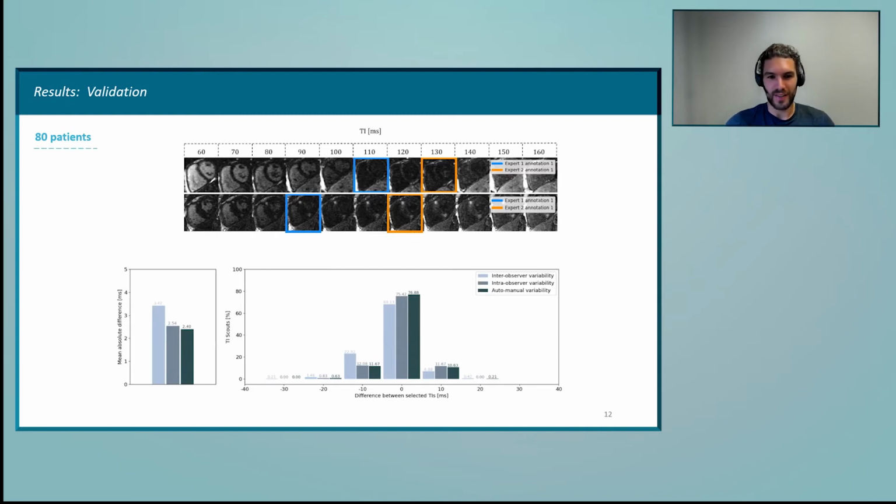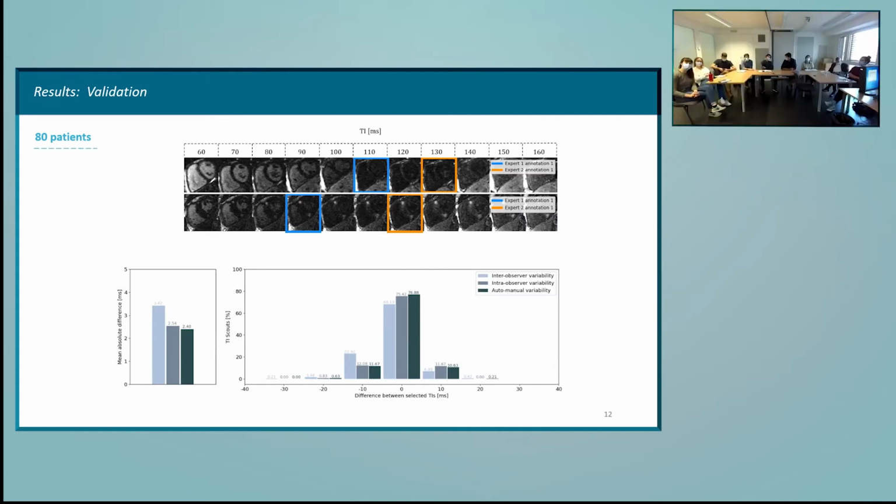But you cannot run the acquisition for the same patient exactly with two different TIs, as you mentioned. So it's difficult to quantify the impact of the TI selection on the final images. For instance, with a 16 millisecond difference you will have a great difference, but with 10 milliseconds, it's hard to know how much it will improve. Maybe another thing one can do is to test some random differences, to figure out what's the unacceptable error on the final image quality and say, yeah, we are within this. That would be a different step. Definitely.